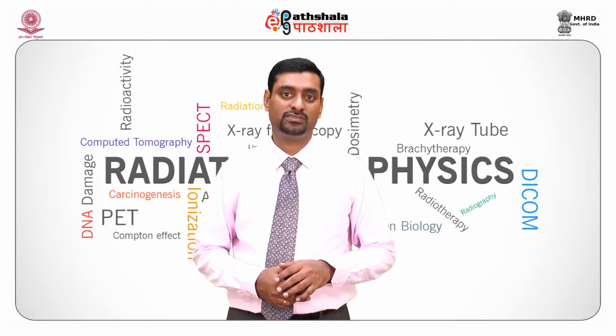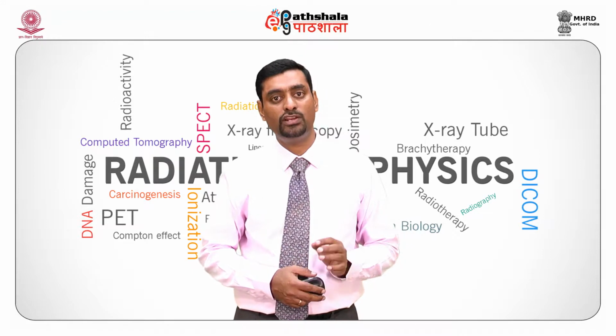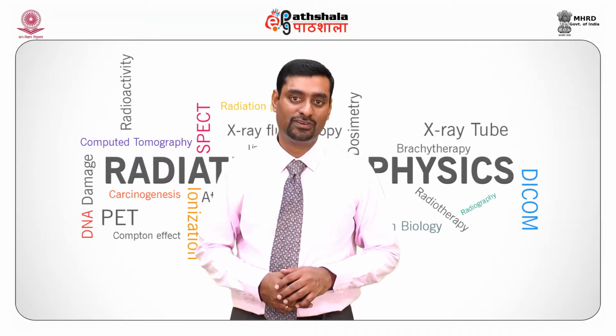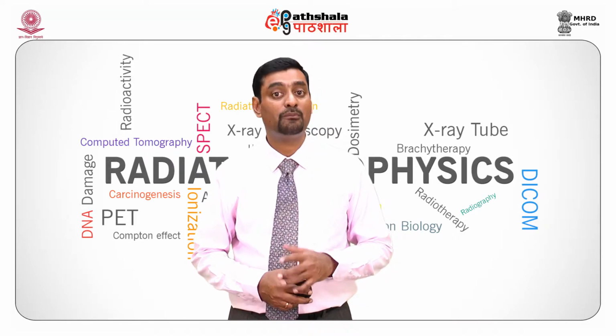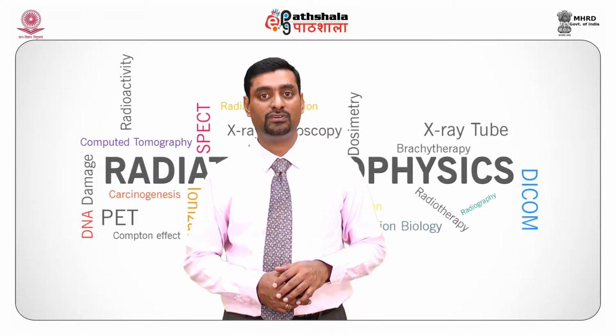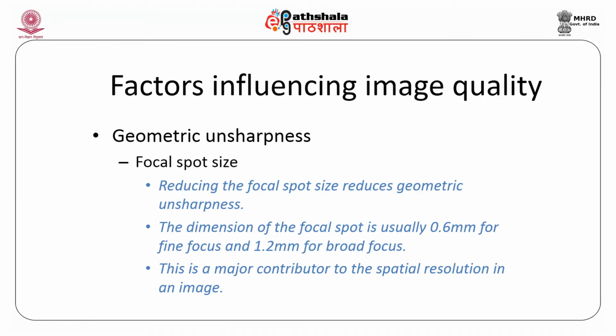For certain procedures, fine focus is used. If you consider mammography, 0.1 millimeter is a fine focus and 0.3 millimeter is a broad focus. So for macro radiography purposes, it is always better to have 0.1 millimeter fine focus in mammography. The dimension of the focal spot is 0.6 for fine focus and 1.2 for broad focus in ordinary X-ray machines. So the focal spot is a major contributor to spatial resolution.